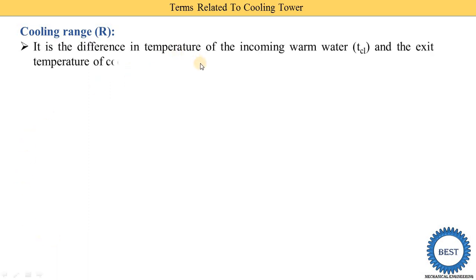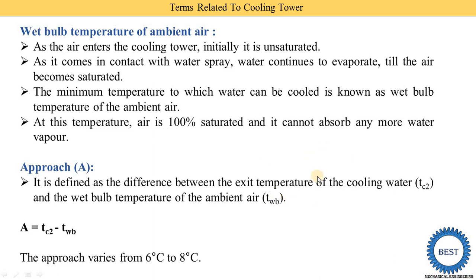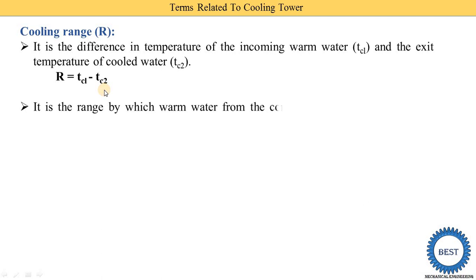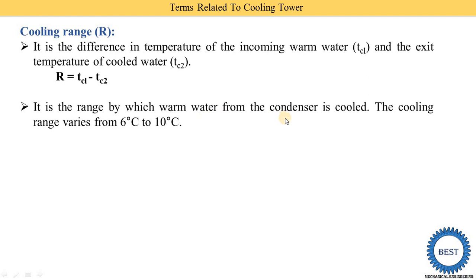The third point is the cooling range, denoted by capital R. It is the difference in temperature of the incoming warm water and the exit temperature of the cool water. R = TC1 − TC2, meaning it is the temperature difference of the water. In the cooling tower, we reduce the temperature of water using air. The incoming warm water has temperature TC1, and after cooling it becomes TC2. So TC1 − TC2 is called the cooling range R — the range by which warm water from the condenser is cooled.